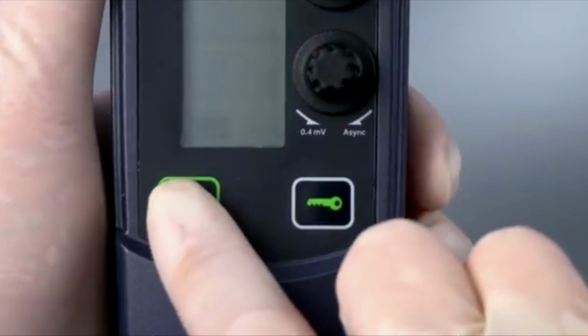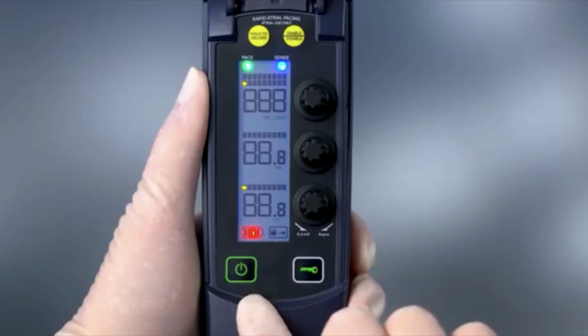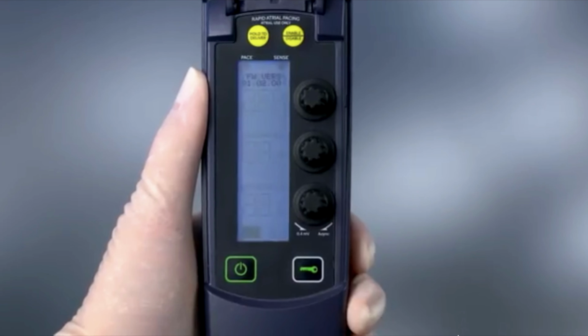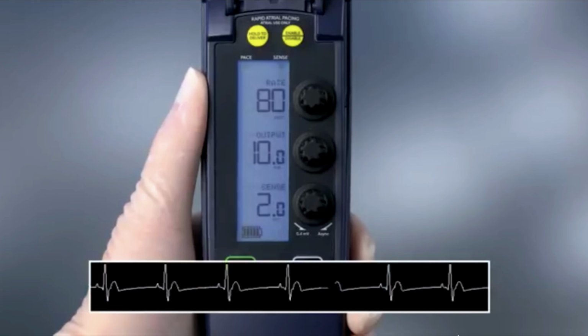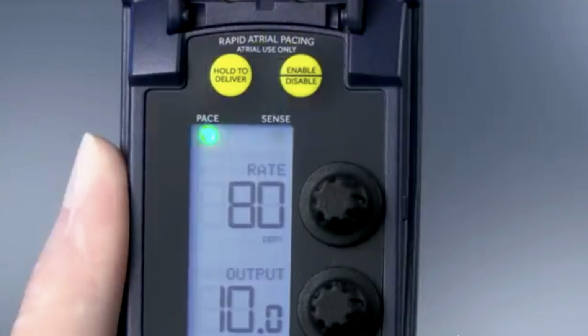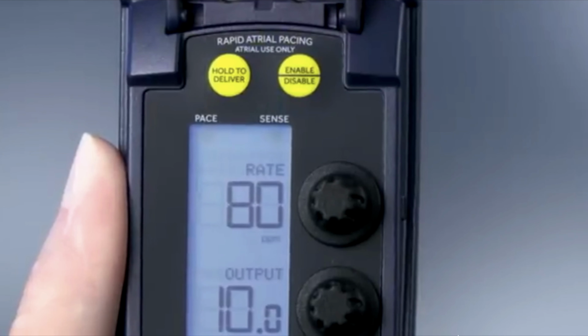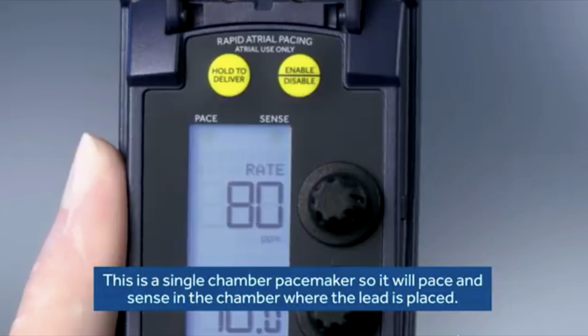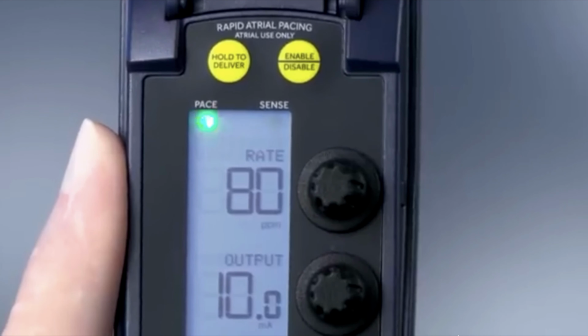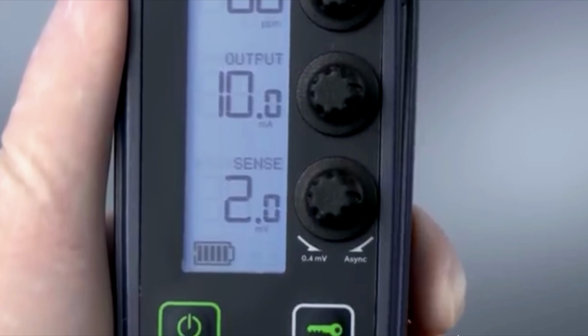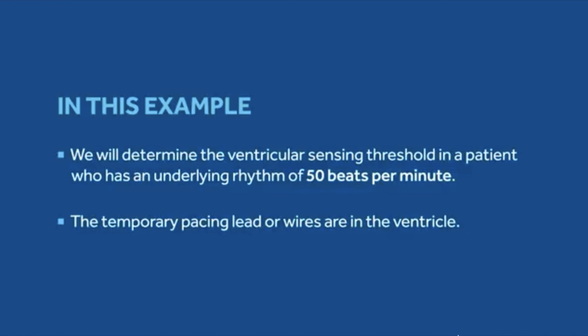To perform the sensing threshold test, first turn on the temporary pacemaker without connecting it to the patient lead system. Ensure the patient is connected to an ECG you can monitor during the testing. When the temporary pacemaker is initially turned on, it will begin sensing and pacing in AAI or VVI mode with nominal values of a rate of 80 ppm, output of 10 milliamps, and sensitivity at 2 millivolts. In this example, we will determine the ventricular sensing threshold in a patient who has an underlying rhythm of 50 beats per minute. The temporary pacing lead or wires are in the ventricle.